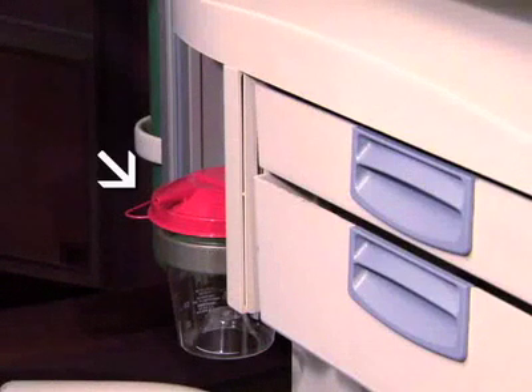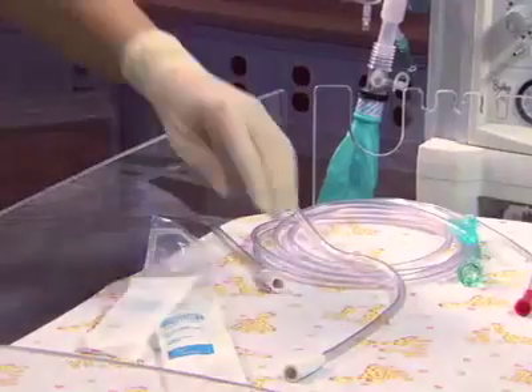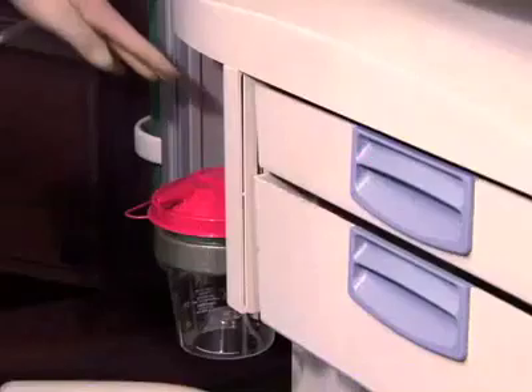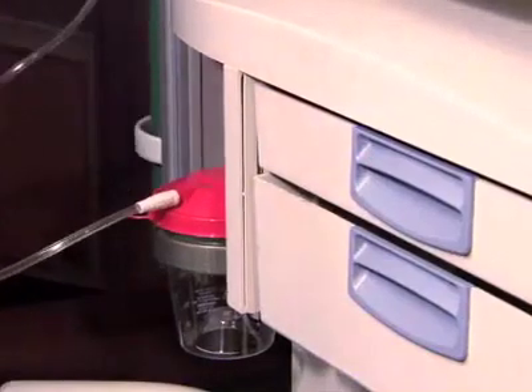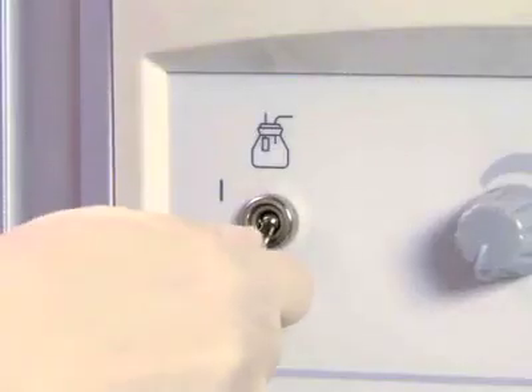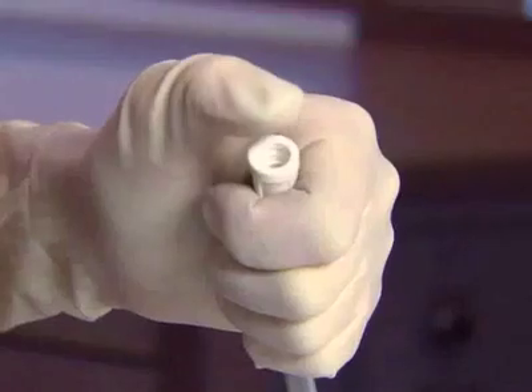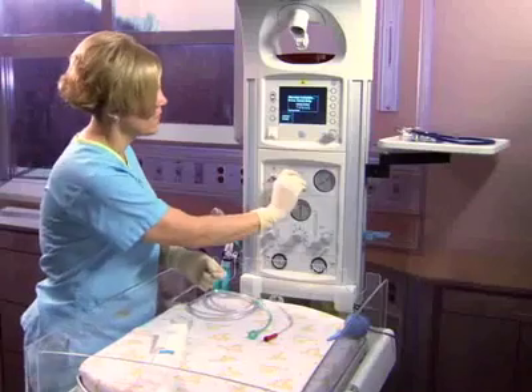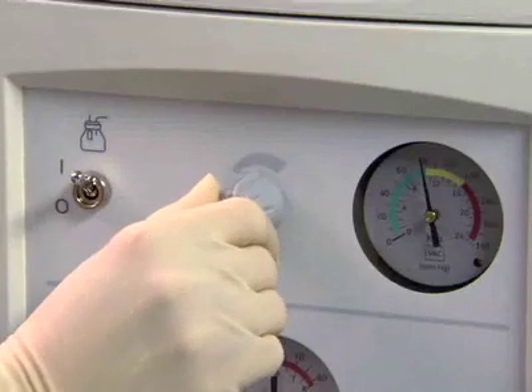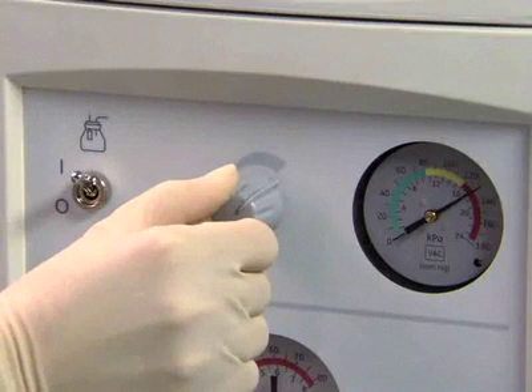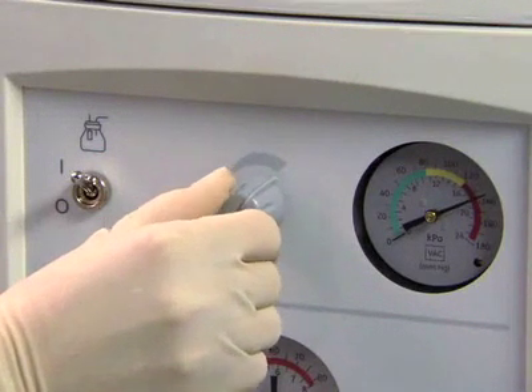Check that a clean suction canister is properly installed and attached to the tubing in the dovetail rail. Attach desired length of suction tubing to the suction canister. Turn the suction control switch on. Occlude the connective tubing, then adjust the suction control knob to a desired pressure between 60 to 120 millimeters of mercury.